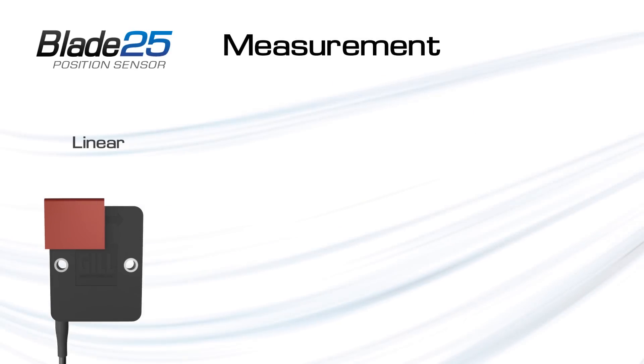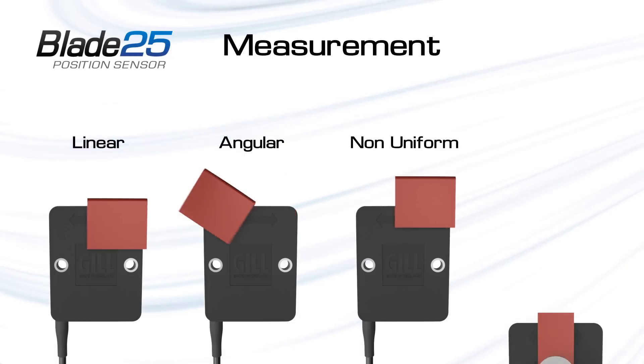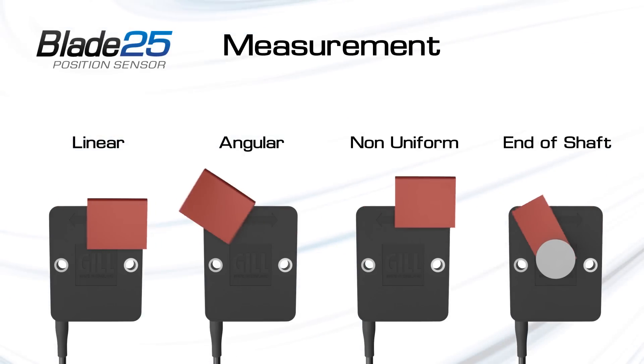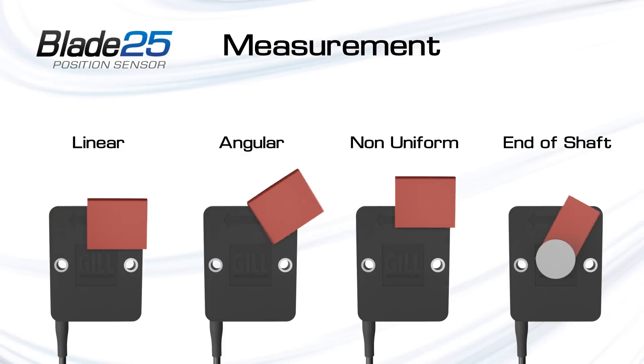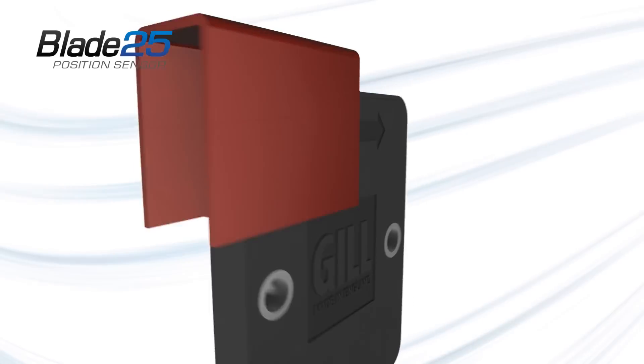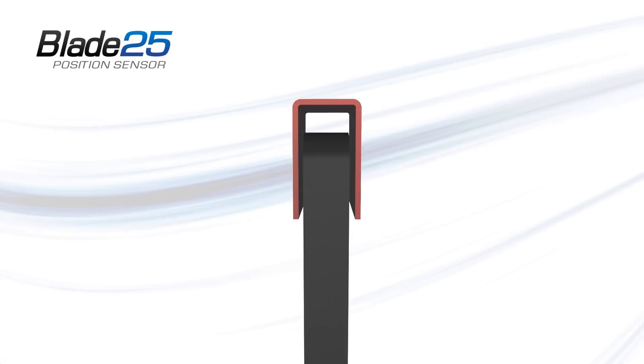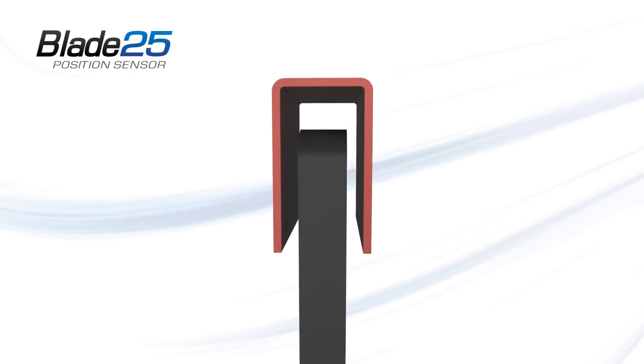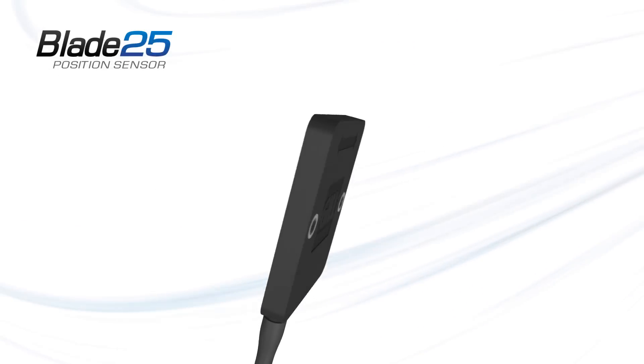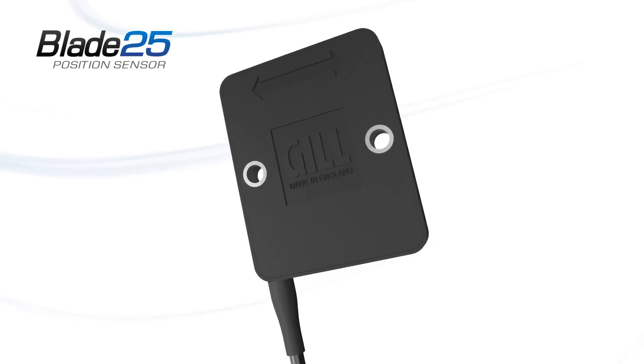This measurement principle allows Gill position sensors to be used for a wide range of measurement types, with no inherent mechanical limit or need for mechanical control. The constant air gap between the sensor and activator ensures the sensor will not deteriorate through use, and unlike Hall effect technology, induction technology is unaffected by the presence of permanent magnets or the Earth's magnetic field, and will not drift with temperature.